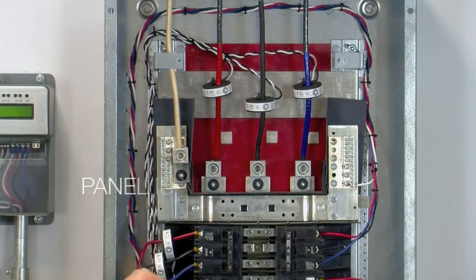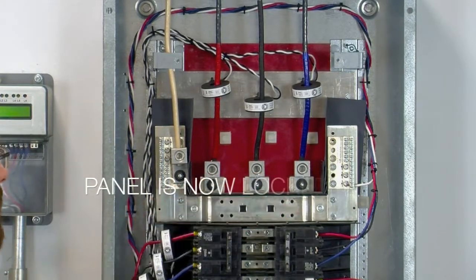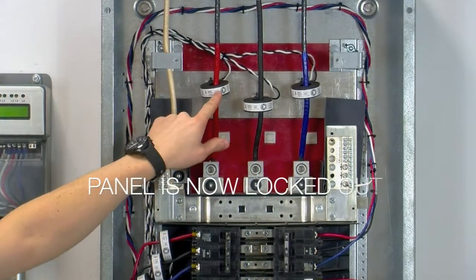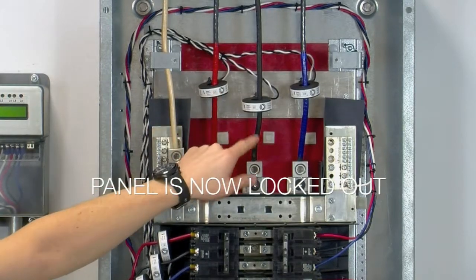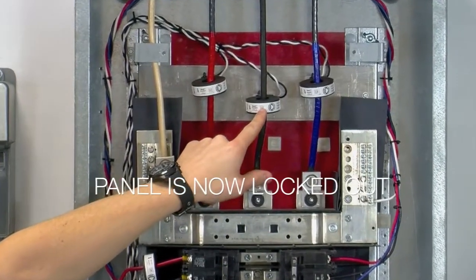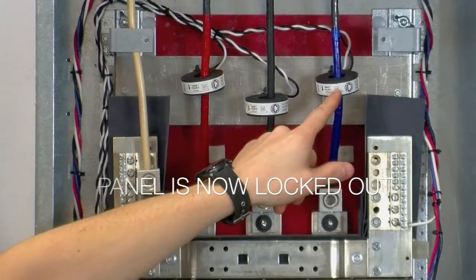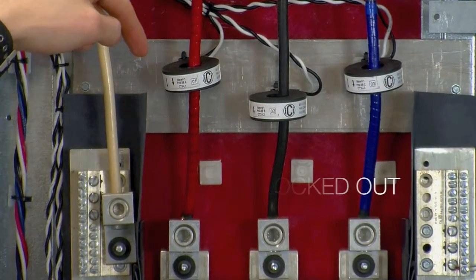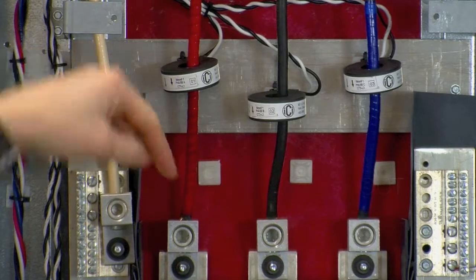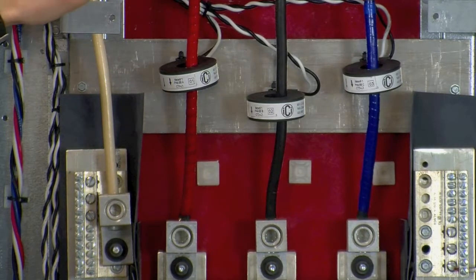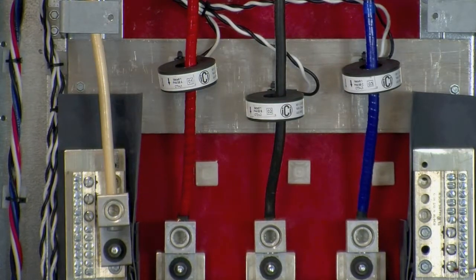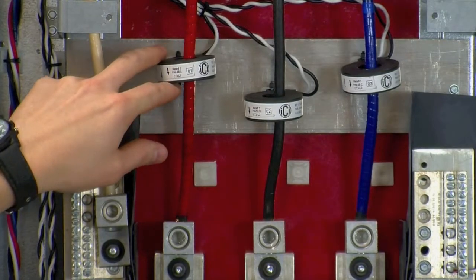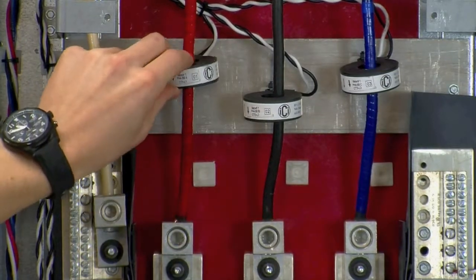Starting at the mains, use an Allen key to loosen off the lugs. We're going to install CT1 on phase A or line 1, CT2 on phase B or line 2, and CT3 on phase C or line 3. Note that the direction arrow must point in towards the breakers, as current flows in from the top of the panel down into the breakers. You can use adhesive mounting pads in combination with zip ties to hold the CTs firmly in place.